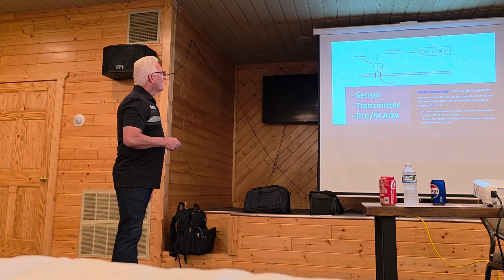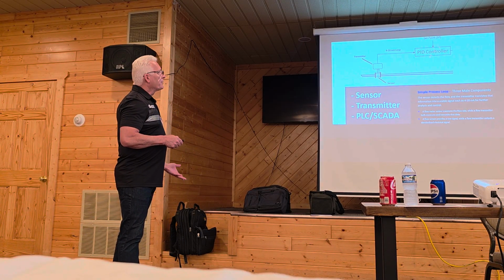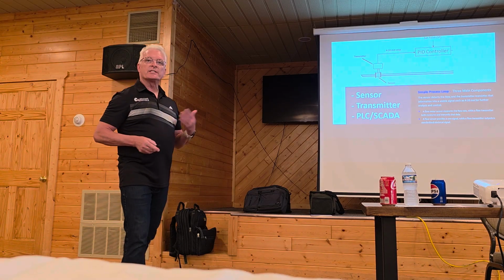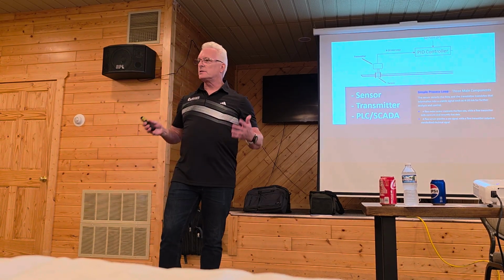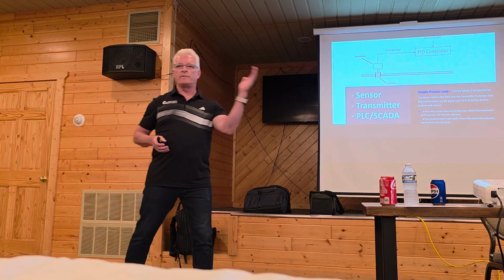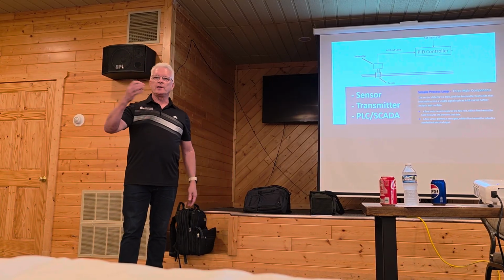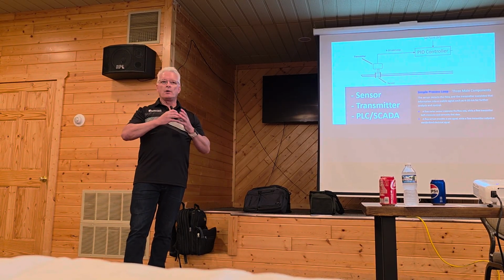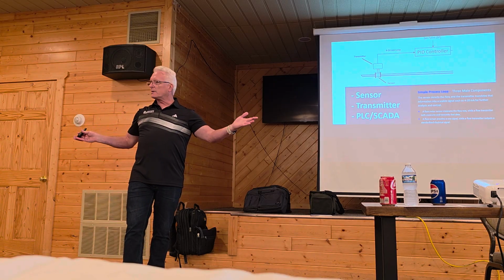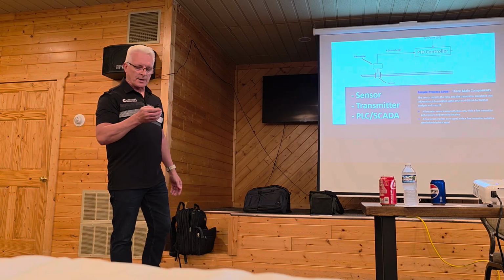So that 4 to 20 comes out and can go to a PID controller, that could be a PLC, that could be a SCADA, whatever makes the decisions to operate your plant, whether it's a valve opening and closing, whether it's feeding chemicals, whatever it is. All that has to be zeroed and spanned, they call it, correctly in order to work properly.